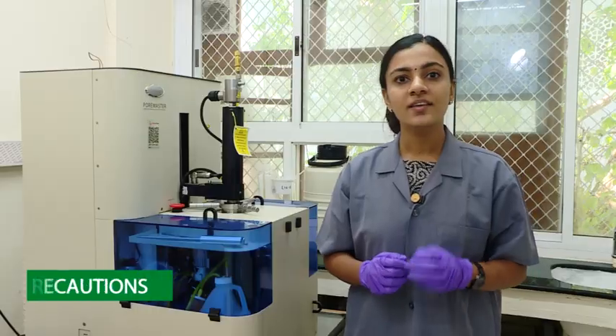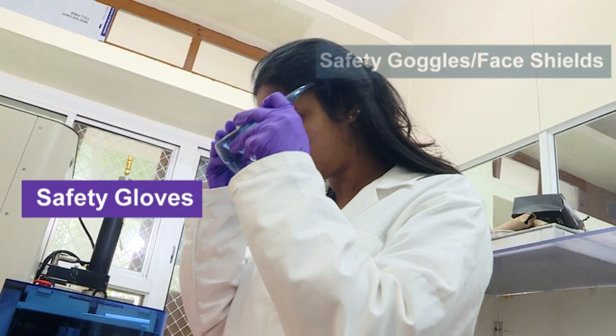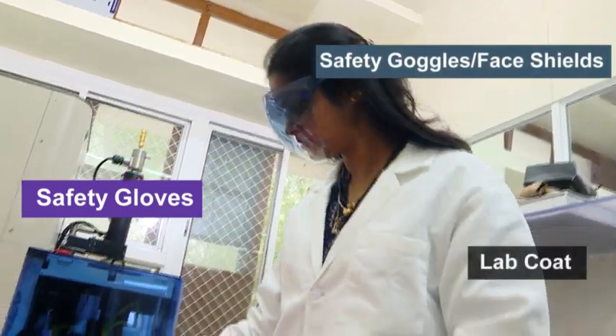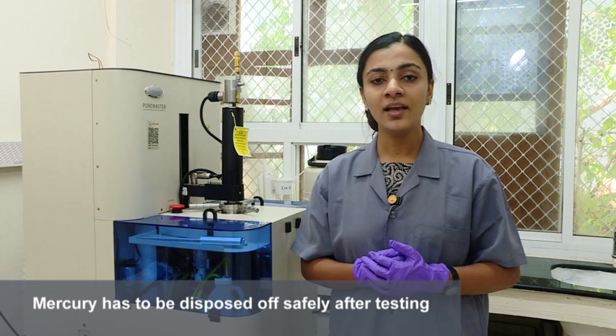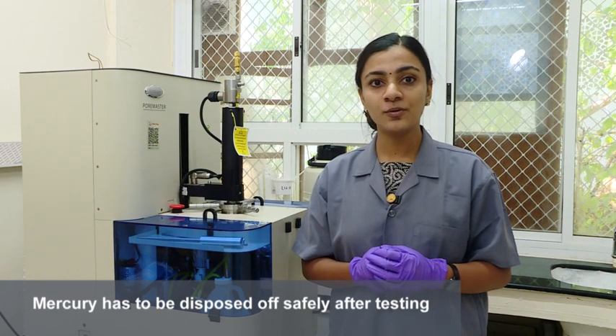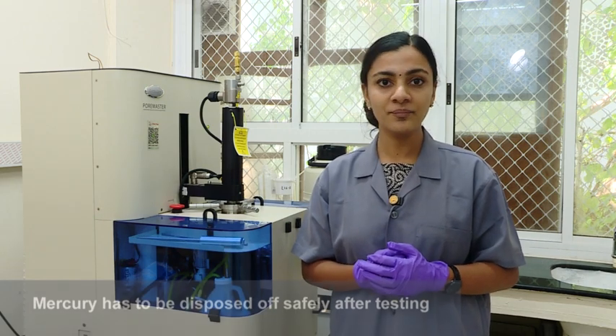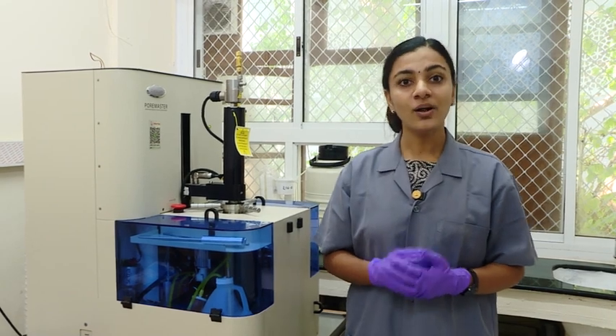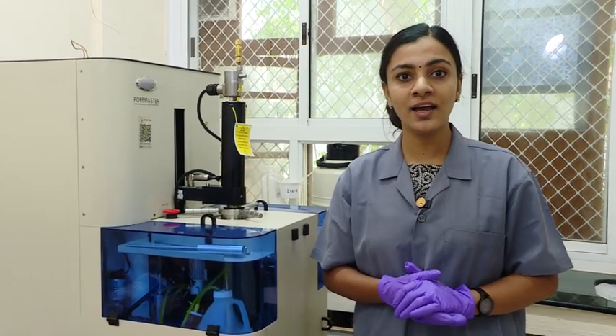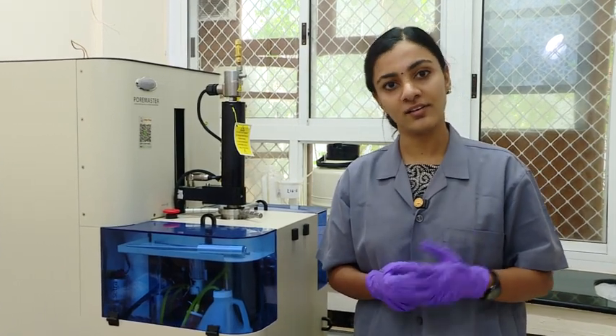Several safety precautions have to be followed while performing testing in MIP. Safety gloves, glasses and lab coat should be worn every time. The mercury has to be disposed of very safely after testing, and also all the cleaning has to be preferably done outside in a fume hood because we are using isopropyl alcohol for cleaning.